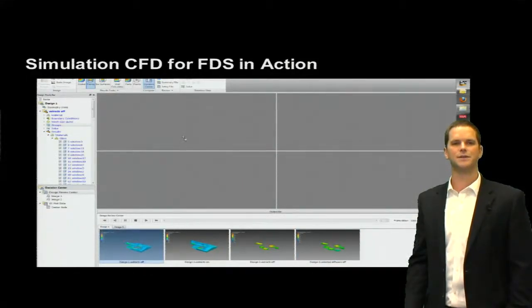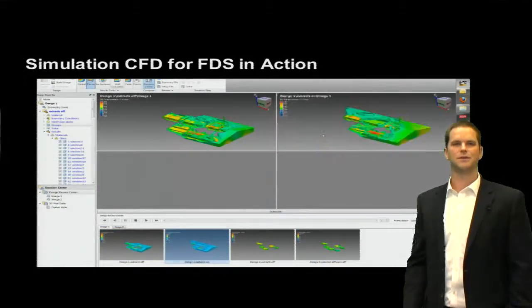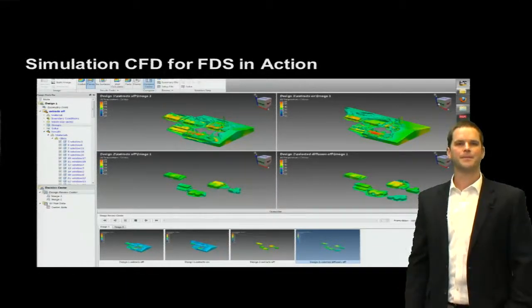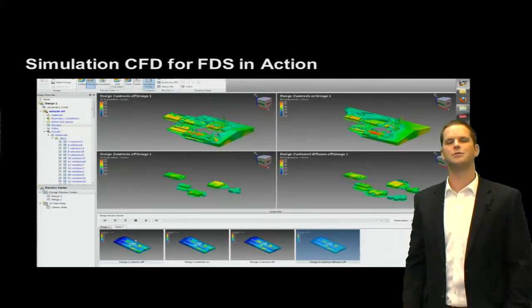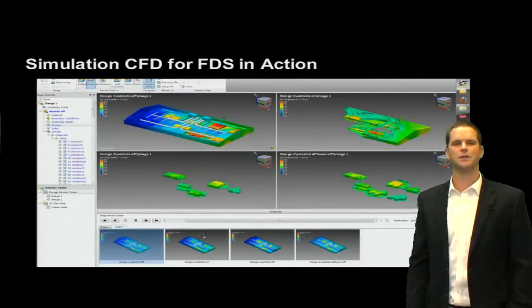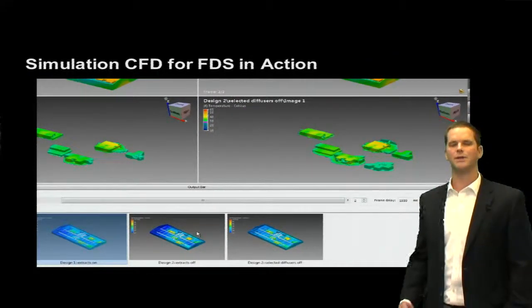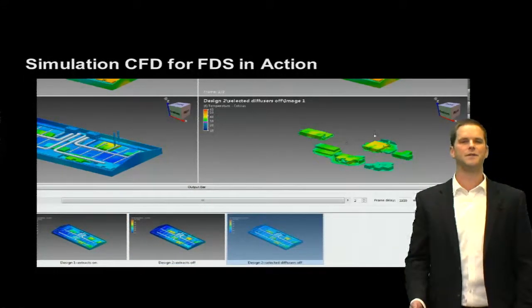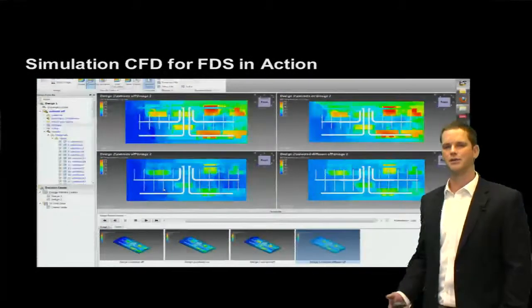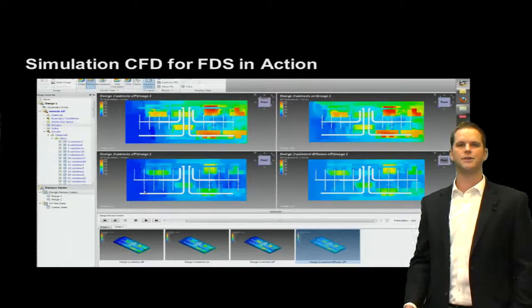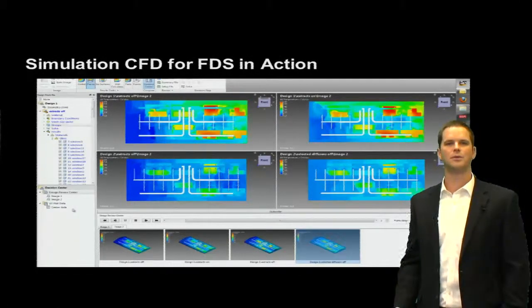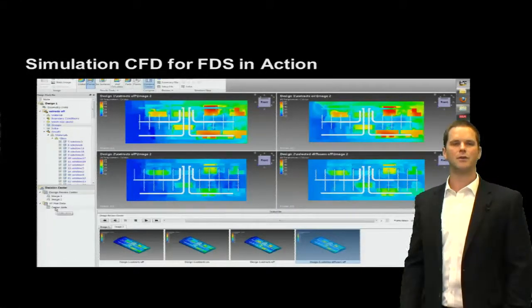Now we go back and make some changes to the ventilation system. We've actually run 4 factories in their entirety — queued these up and run them overnight. We come back in the morning and the results are ready. We can see areas that are too hot or too cold, and the volumetric aspect of those has been reduced. Looking at these 4 factories gives us a clue as to how the ventilation system should be set up, where we might turn registers on or off — getting into the energy saving aspect. We guarantee safety first, knowing we're ventilating properly, capturing pollutants with hoods. Once we've dialed that in, we can dial back energy consumption by reducing ventilation requirements to lower running costs day over day and year over year.